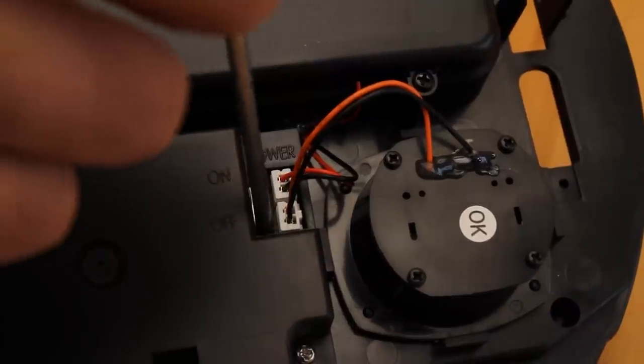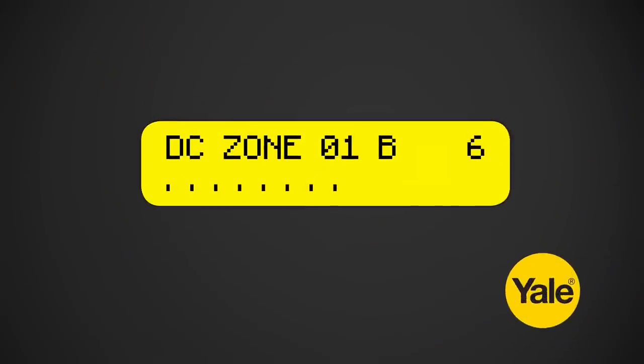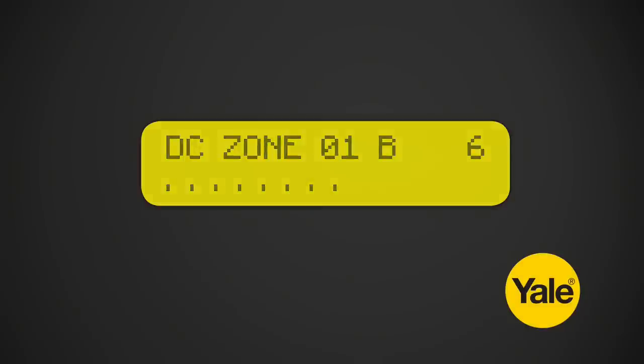Slide the switch to the ON position inside the siren and press the test button. If the sensor signal reached the control panel, the screen will briefly display a message like this. The radio signal strength is shown by a number in the upper right corner of the display. Please note, the number ideally needs to be 5 or more for optimal signal performance.